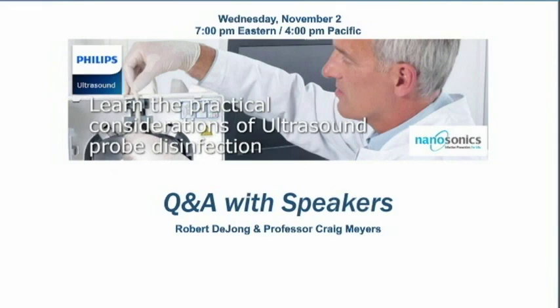Great, thank you, Craig. So we've got another question here on hydrogen peroxide wipes. Do you know if we can use an H2O2 wipe on the probe surface and intracavity? So I might take this one. There are wipe products available in the US that are low-level disinfectants and intermediate-level disinfectants, and they could potentially be used on a surface probe so long as the probe manufacturer IFU says that it's okay, because sometimes the chemistry could interact with the plastic, so you need to check that.